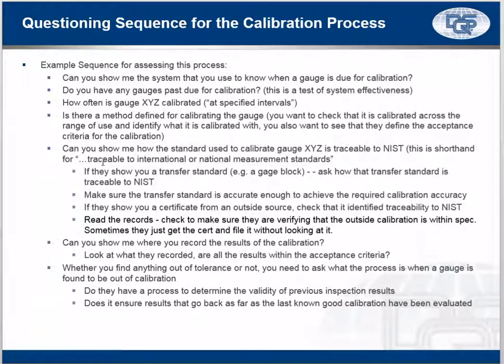When you see them do this, you want to know that the standard they're using to calibrate something is traceable to NIST. I'm using shorthand here. Traceable to international or national measurement standards is what the ISO standard says. So if you're looking at that caliper and they show you how they do it with a gauge block, your next question should be, oh, since you're using gauge blocks, can you show me that those are calibrated?